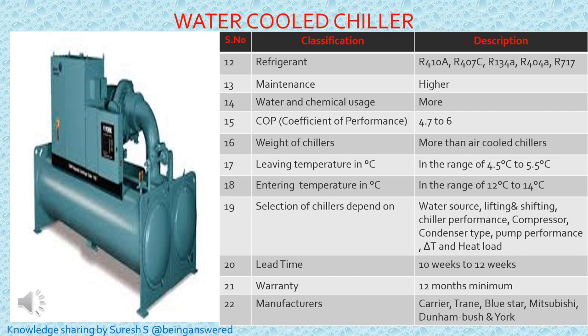Similarly, the selection of chillers depends on many parameters, like water source. Without proper water, you can't go with a water cooled chiller. Similarly, lifting and shifting, and chiller performance, like what type of compressor and what type of condenser they are using, next pump performance, the delta T, and the heat load. Depending upon many parameters, they will select the type of chiller.